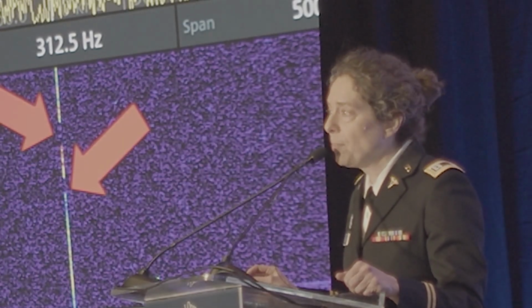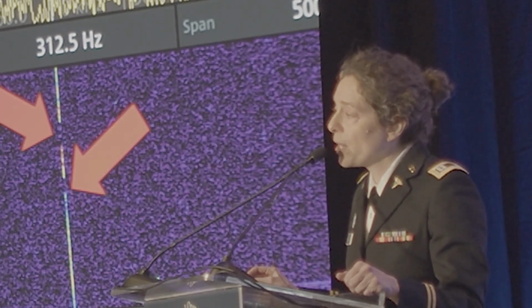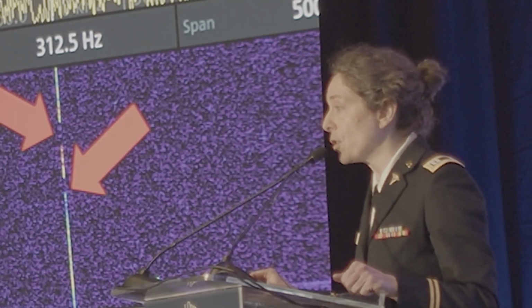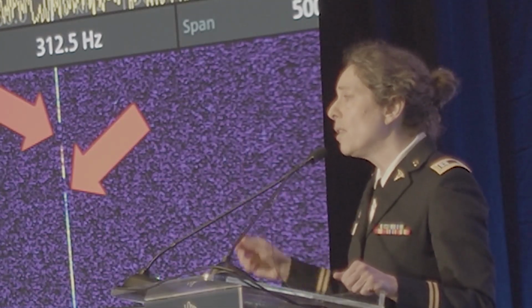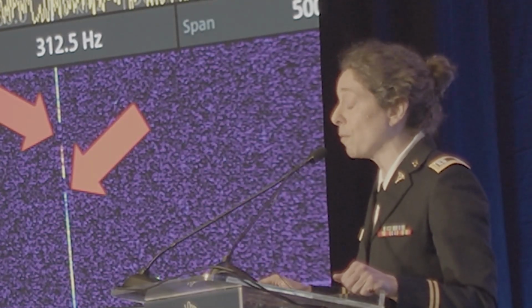That's probably because at the time the signature was taken, the Butterfly probe was transmitting pulse wave Doppler in the 5 megahertz range. Depending on the shielding on the probe, the pulse wave Doppler may generate more radio frequency interference.